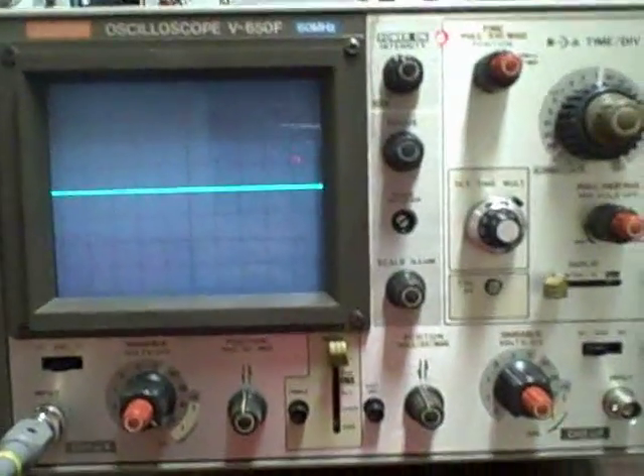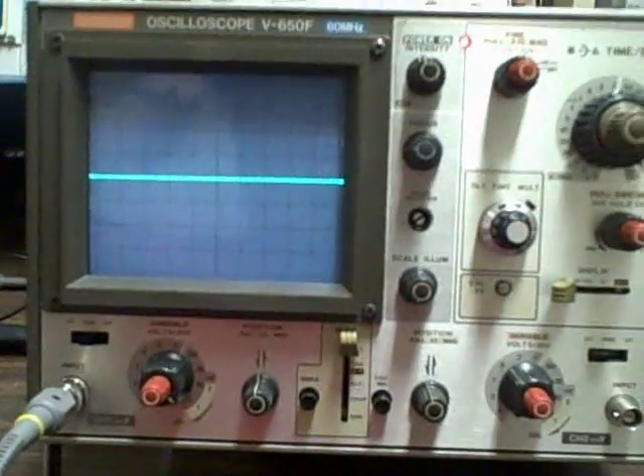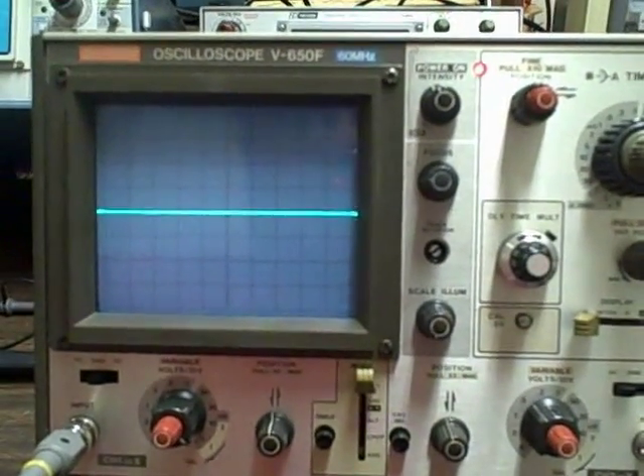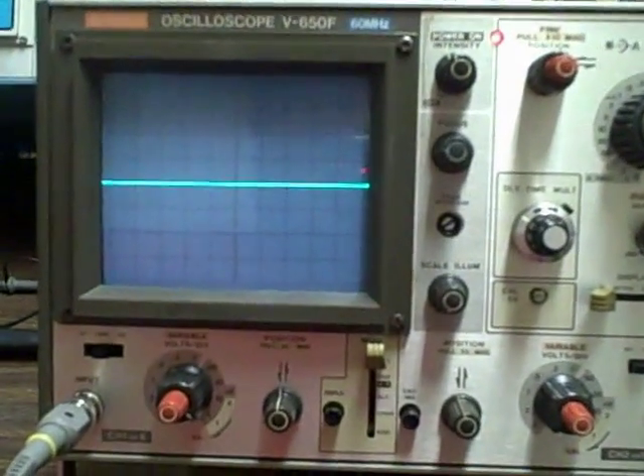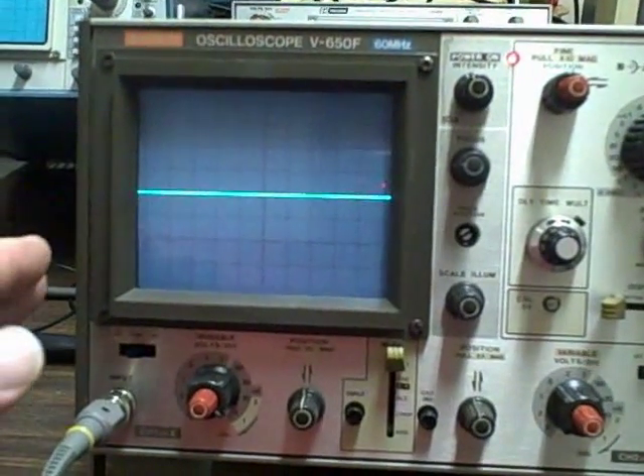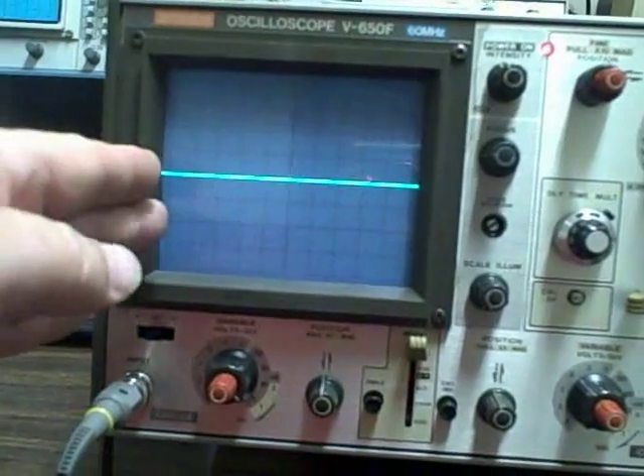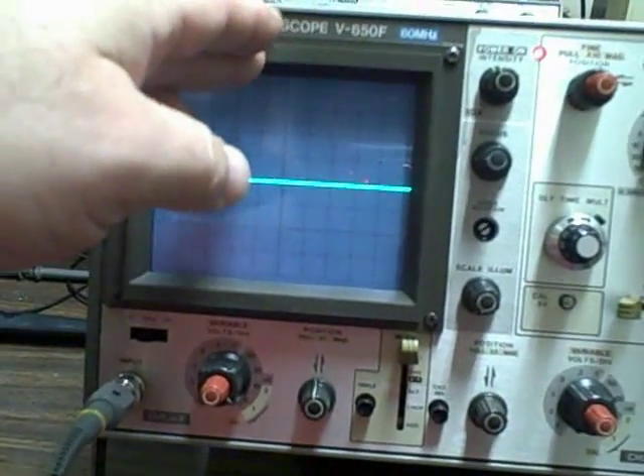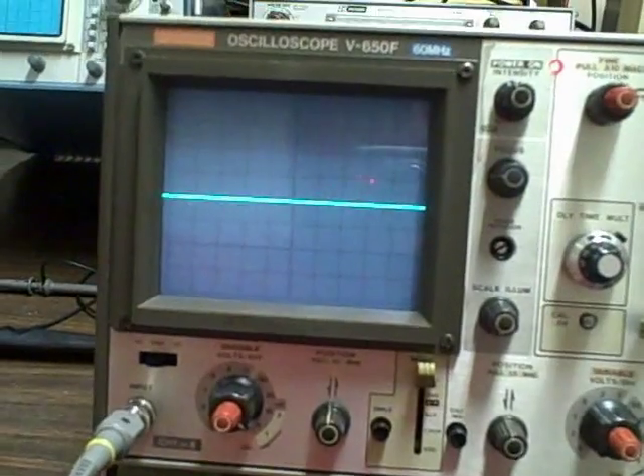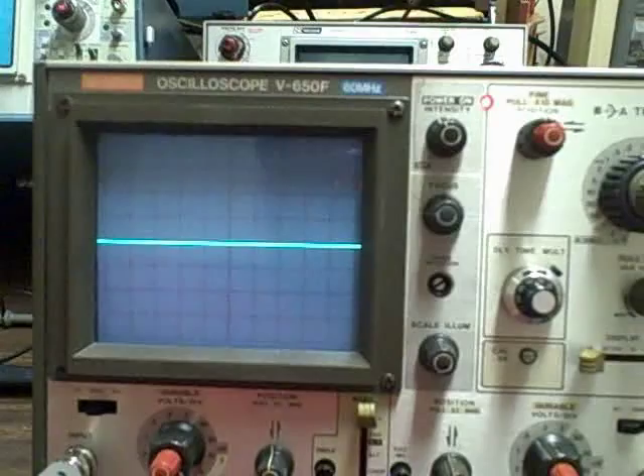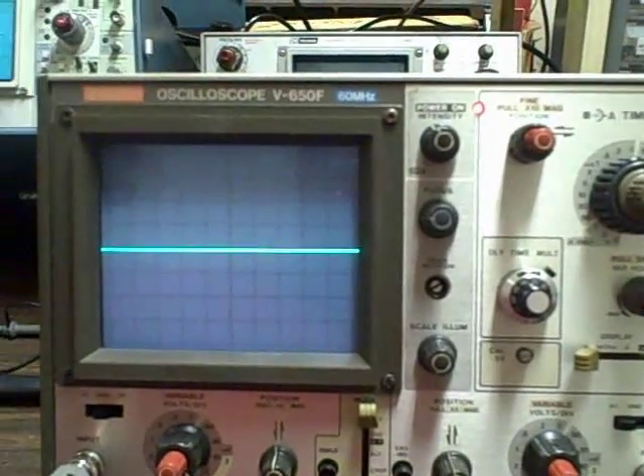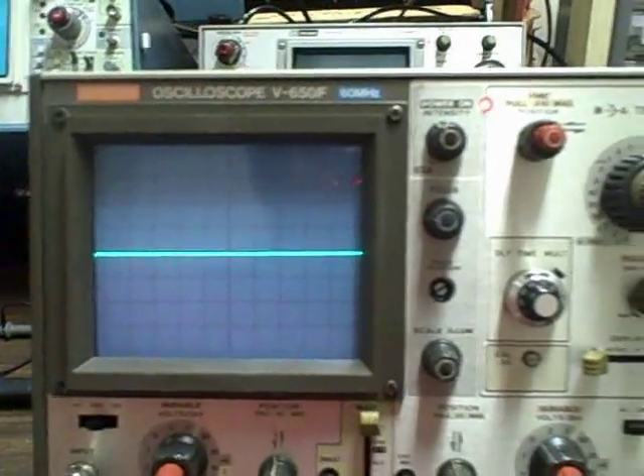One of the obstacles I have here is I have to be able to show you that I can properly read voltages in my vertical positions. And then once I've done that, prove that my time base is sweeping properly. If I can prove linearity where I sweep from zero in a straight line to a known magnitude voltage and then come back down within a certain time period, as long as I'm maintaining that straight line, I know that I am interpolating every point in between accurately. So it's a good representation then at that point that I have linearity and that I'm able to faithfully reproduce my signals.